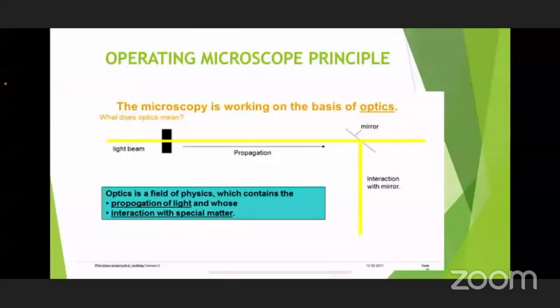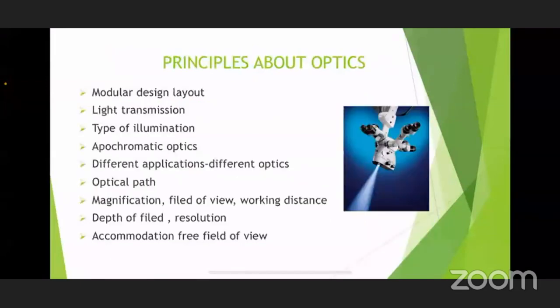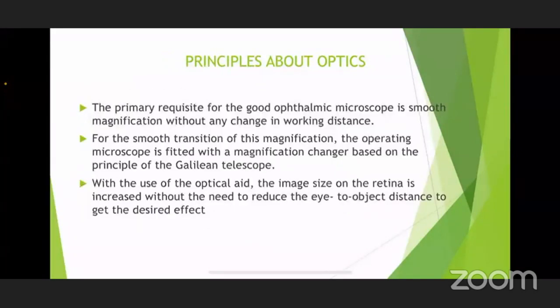The principle of an operative microscope is based on optics. There are various terms used in these optics which we will go through as we discuss the various parts of the microscope. The basic thing to remember is that the purpose of a good operating microscope is smooth magnification without any change in working distance. For this smooth transition of magnification, either we can have a knob giving stepwise magnification, or a zoom system with foot pedal control. The purpose is that, without changing the eye-object distance, we achieve a good image size on the retina for whatever surgery we are doing.